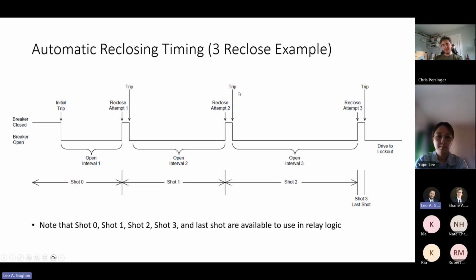Well, whatever caused it is still there. So it trips out again, and we go into open interval 3, which we can see is even longer. And then we have that next reclose attempt, call it shot 2, and then it trips one last time. This particular recloser was only set to 3 reclose attempts. It's not going to give it a 4th attempt, and that's when it will drive to lockout. And that would be shot 3. It would also be last shot.